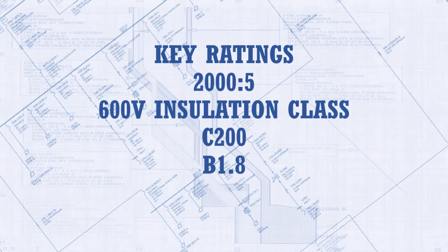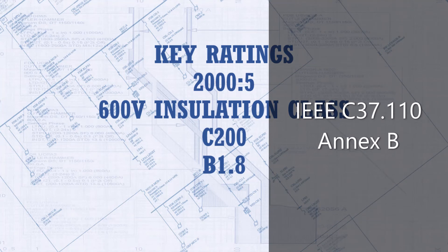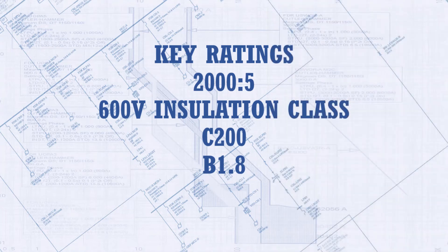Let us quickly recap the key ratings of the CT under testing on this presentation. We have a 2,000 to 5 ratio, 600 volt insulation class ANSI protective relaying accuracy class C200 at a standard burden of B1.8 ohms. It is important to point that the typical standard burden for ANSI accuracy class C200 is actually 2.0 ohms, and by standard we mean a burden at a power factor of 0.5, referred to IEEE C37.110 Annex B. Also, accuracy class is a standard way of describing CT performance. For example, here it means that this CT is capable of delivering 200 volts on its terminal to a standard burden of 1.8 ohms with an error of 10% or less at 20 times its secondary current rating, that is, 20 times 5 equals 100 amps.